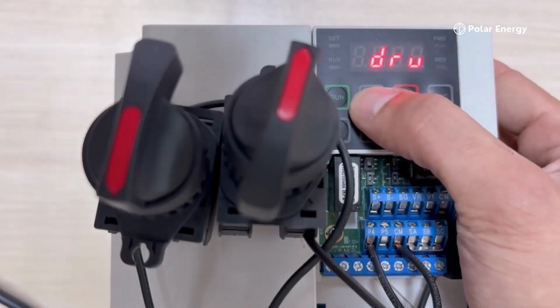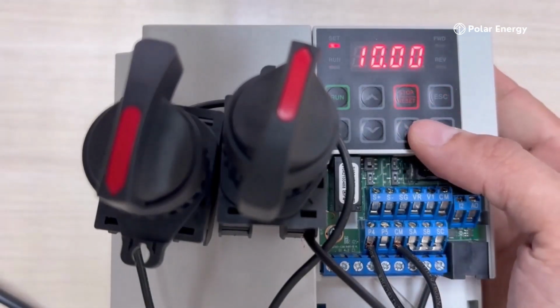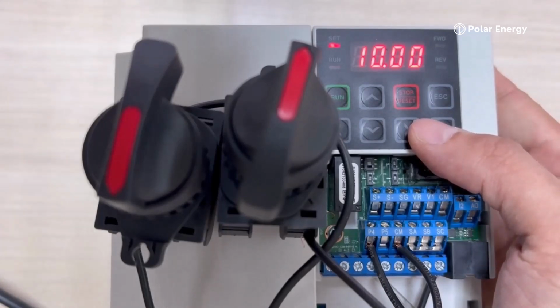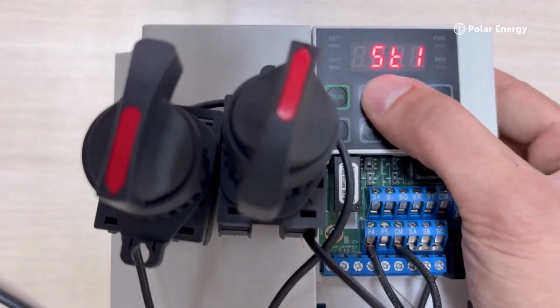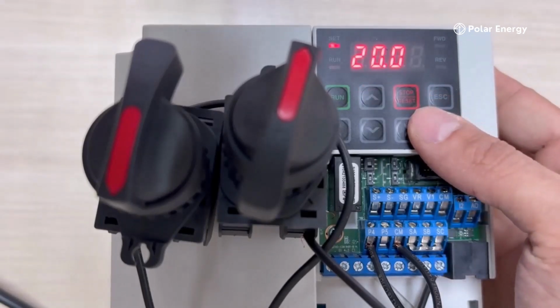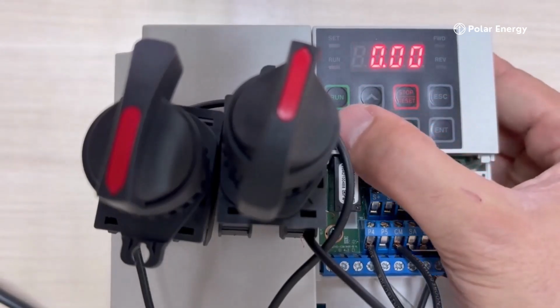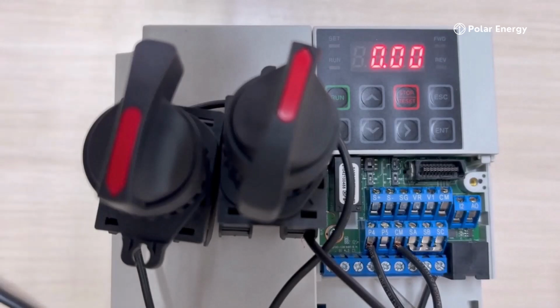You can see its value is 10, so my first speed is 10. Parameter ST2 is my second speed. I enter parameter ST2 and you can see its value is 20. I confirm it and go back. So if my digital input P3 is activated, my frequency will be 10 Hz. And if my digital input P4, which is my second speed, is activated, my frequency will be 20 Hz.